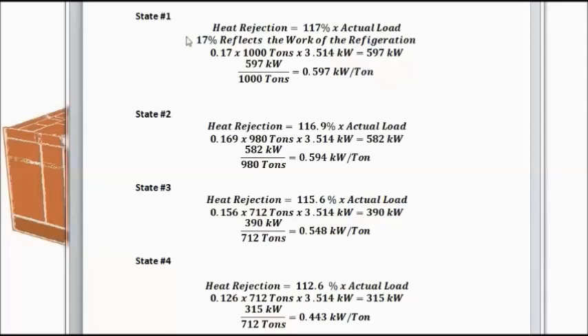So, we took the heat rejection. The total heat rejection is 117% of the actual load. It's the 17% of that, though, over the actual load is the work of the refrigeration, as I pointed out. And so, we can calculate this, convert it to kilowatts, and we get 597 kilowatts. And, of course, if we put that over the unit capacity, we get 0.597 kW per ton.